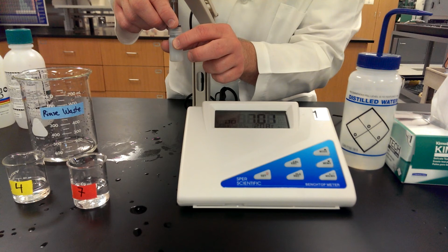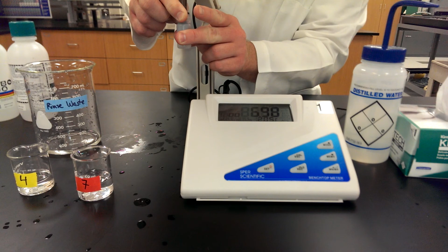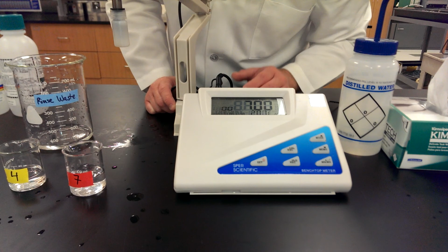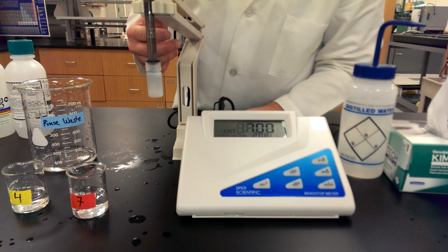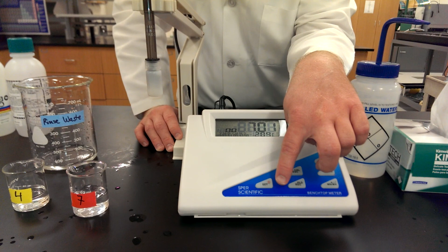Alright, so I'm going to put this back by sliding it up. And then I'm just going to twist it, that cap with the pH 7 buffer in it, and there we go. It's reading 6.98, not 7.0, but again, that's okay. It'll probably say 7.0 at some point. There you go. So here we are. We have a calibrated pH meter. It's ready to use now, or it's ready to store, which is my case. So go ahead and turn that off by pushing the power button. And there you go. That's how we calibrate a pH meter.